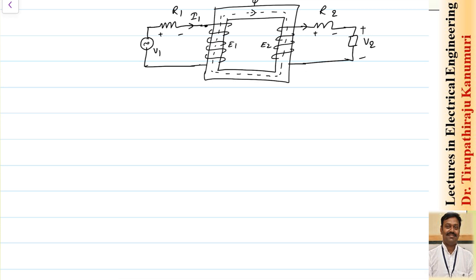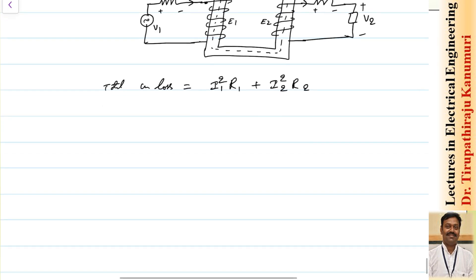There will be a power loss because of this resistance, dissipated in the form of heat. This is called copper loss - even though nowadays aluminum is sometimes used, it is still called copper loss. The total copper losses are: I1²R1 in the primary winding and I2²R2 in the secondary winding.